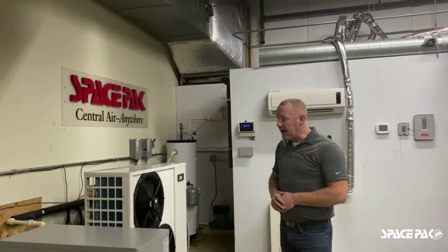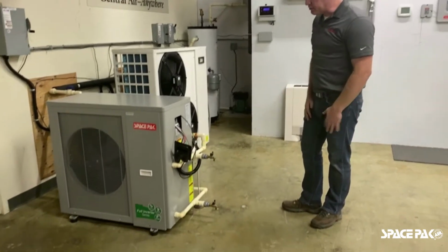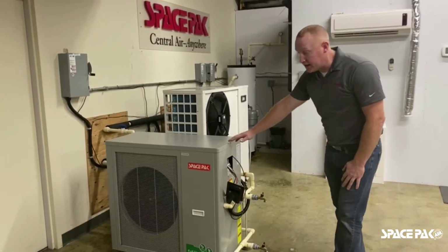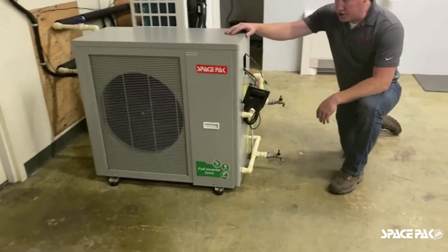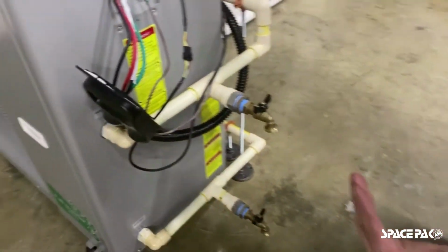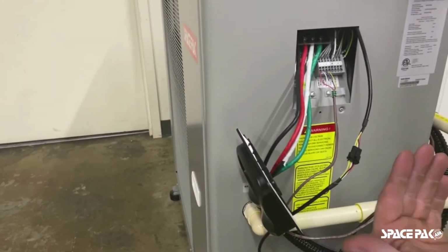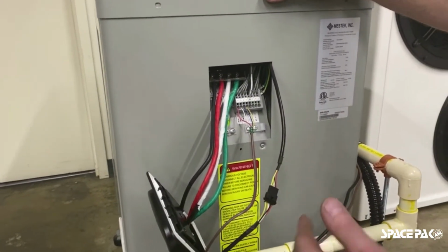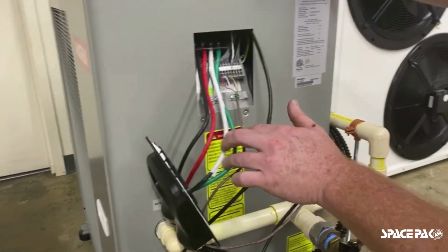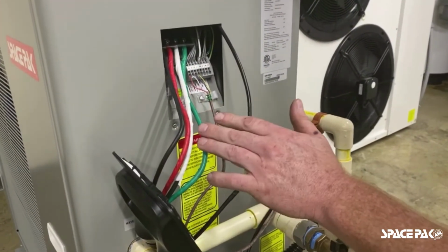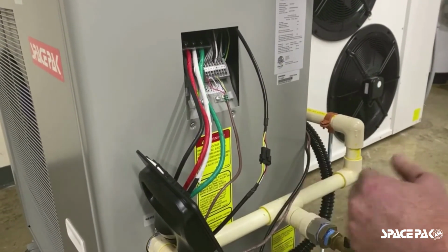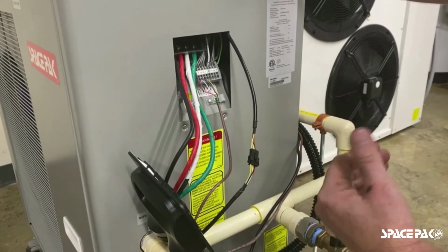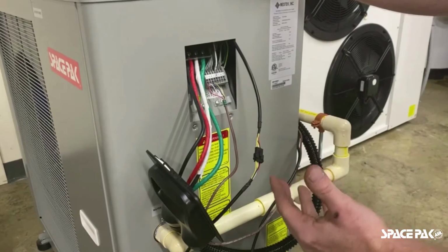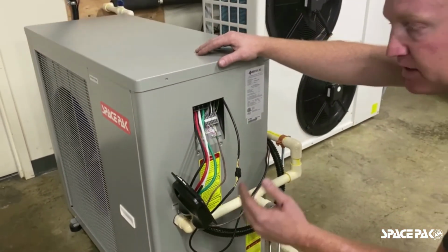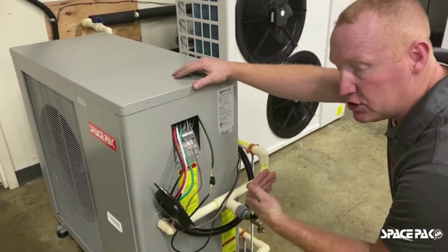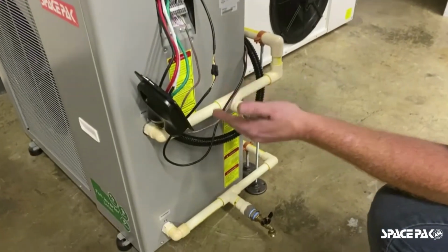Okay, so we have finished our unit swap out here at the Reed Institute in Westfield, Massachusetts, SpacePak training headquarters. Bring ourselves right down in here. We'll go over what we did to lay out our line voltage wiring as well as our control wiring. You can see here, as described earlier in the video, we have 240 volts, 220 volts here supplied to this unit. 2 hot legs, a neutral, and a ground. Now it's important to make sure that we use a neutral. We want to use a neutral because we need that to assure the proper operation of the system's circulator, right? The circulator that's going to be placed between the heat pump itself and the buffer tank. So again, we just want to be sure that we have a neutral installed in the system, neutral and ground.